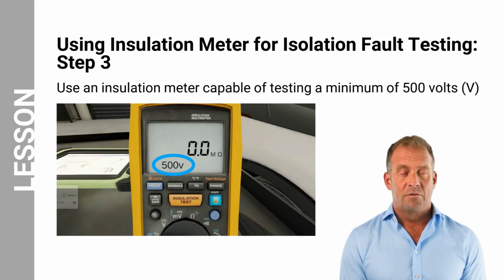Step 3. Choose an insulation meter capable of testing at a minimum of 500 volts. Before use, ensure that you read all instructions and warnings for your insulation meter. The available test ranges for this meter are 50, 100, 250, 500, and 1000 volts. Choose the range button for your meter to display 500 volts.